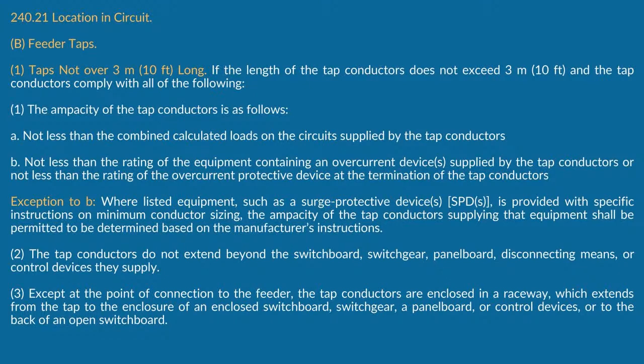There was a certain individual after that who just could not let the whole thing go. It turned out being a 1500 amp bus section, and they wanted to take number 8s off that 1500 amp bus section, go to a 60 amp disconnect, then go to a piece of equipment. I said okay, let's see what James has to say about it—I think we brought it up to you on NEC Live. Then you said, oh yeah, it was like a number 4, I think. Yeah, I showed how to do that. As long as it was a number 4 to that 60 amp disconnect, you're good to go.